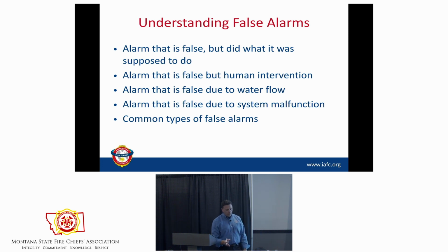And I'll give you a good, for instance, one of our high schools in Michigan. We have the State Fire Marshal Office. State Fire Marshal Office does all of our schools. We have very little technical authority, but we do get a little aggressive once in a while. And you have to have smoke detection near kitchens. So they had what was a popcorn machine. In every home basketball game, we would go on an activated smoke detector outside the concession stand for what? Making popcorn. Every time. There's nothing like filling a varsity basketball game and then us coming and them having to dump. So we said, let's move it or change the technology, right? There were things we could do, right? But that's the detector doing its job.